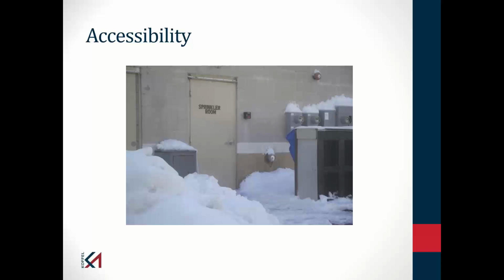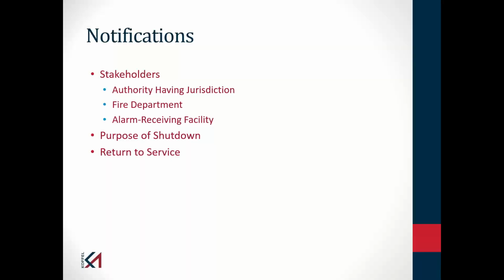As an owner and a contractor, you need to understand where the contractor needs to go and develop a plan to allow them to have access to the required spaces. If you have a reason to shut down your system, you are required to notify the authority having jurisdiction, the fire department who's responsible to respond to a fire at your location, and, assuming your system is monitored by an alarm receiving facility, the alarm receiving facility. You'll tell them why the system shut down, and then you'll notify them when the system goes back in service.